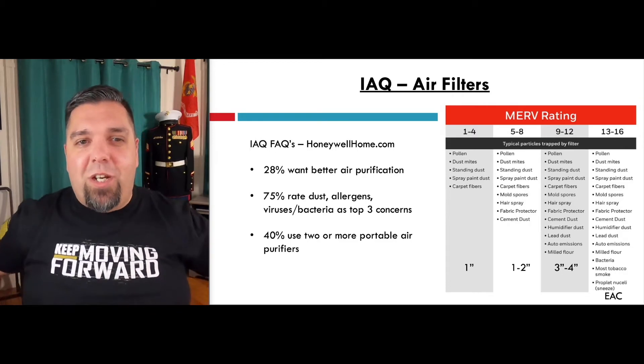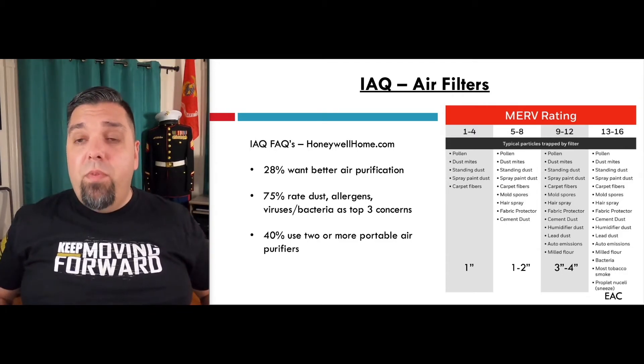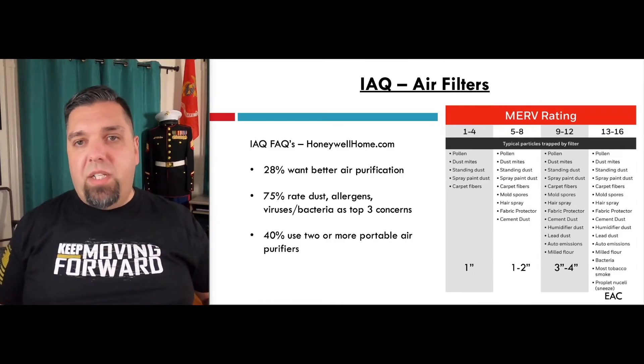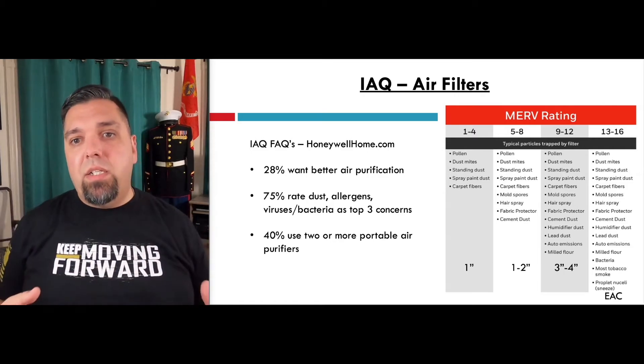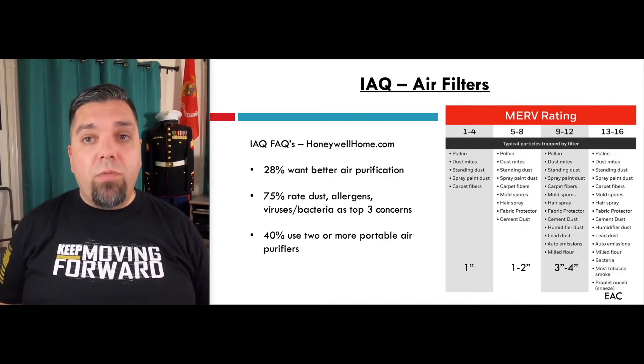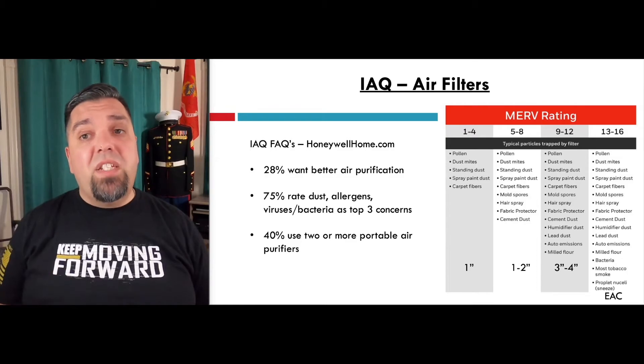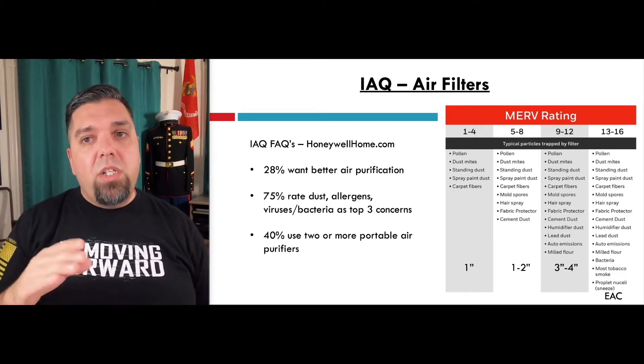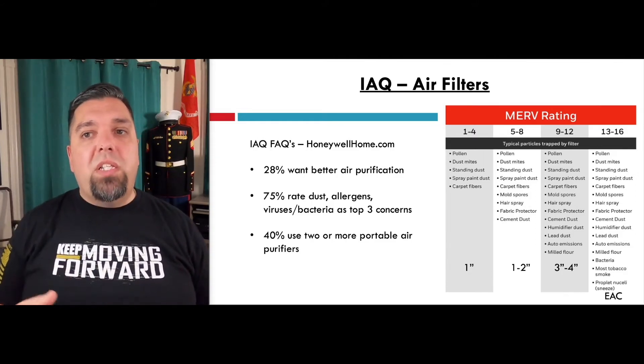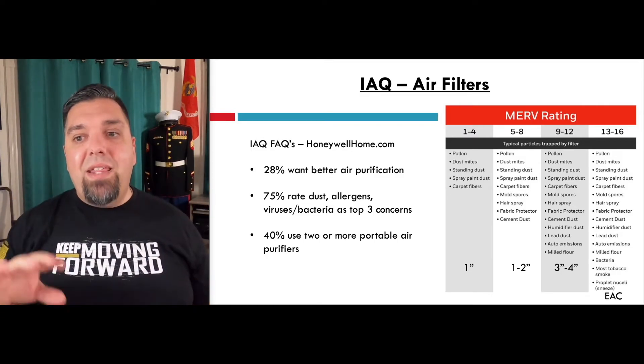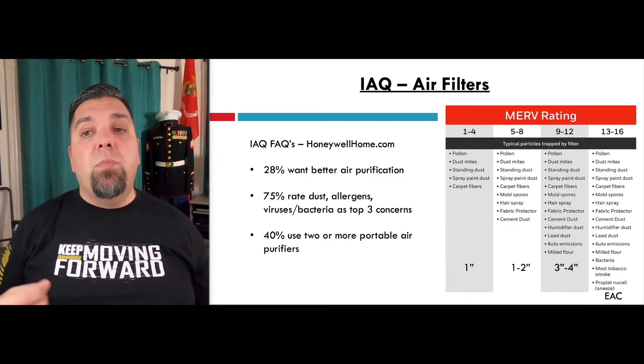Let's talk about air filters and IAQ filters. This chart is from Honeywell Home, and it's easy to find MERV rating information. MERV 1–4 picks up dust, pollen, carpet fibers, and big particles — that's usually a one-inch filter. Above MERV 4, you really should have a two-inch or larger filter; most commonly you'll see color-coded pleated filters. White is usually MERV 6 or 8; MERV 7 is blue. Those pick up mold spores, cement dust, dust mites, and finer particles. For MERV 10 or 12, you really should have a three- or four-inch filter box or accordion style. Anything higher than that in MERV rating is most likely an electronic air cleaner.